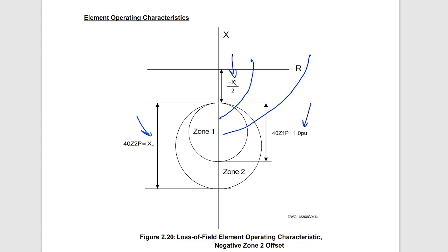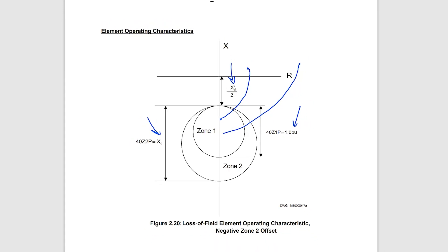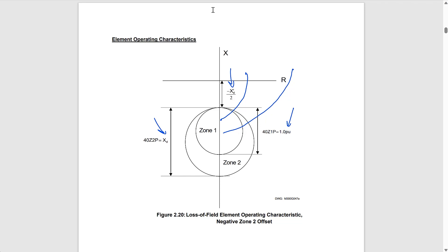These mho elements also have time delays. A typical delay for zone one is 0.1 seconds, used to prevent misoperations during switching transients, and a typical delay for zone two is 0.5 seconds, used to prevent misoperations during power swings. To summarize: negative offset = ½ X'D, zone one diameter = 1 per unit on machine base, zone two diameter = XD, with delays of 0.1 s and 0.5 s respectively.